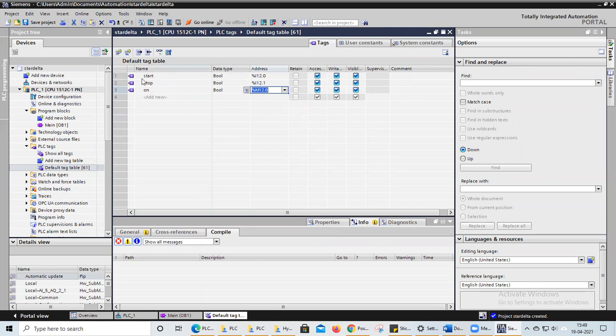This is regarding my latch circuit. I want the latch to be in this format. And now I will have three coils. One is the main coil, one is the star coil, one is the delta coil. The star coil has to be energized in the beginning. After some time, the delta coil has to be energized. That is my priority. So I need to have one main coil. I will write it as main coil, and it is my output. Main coil is my output.